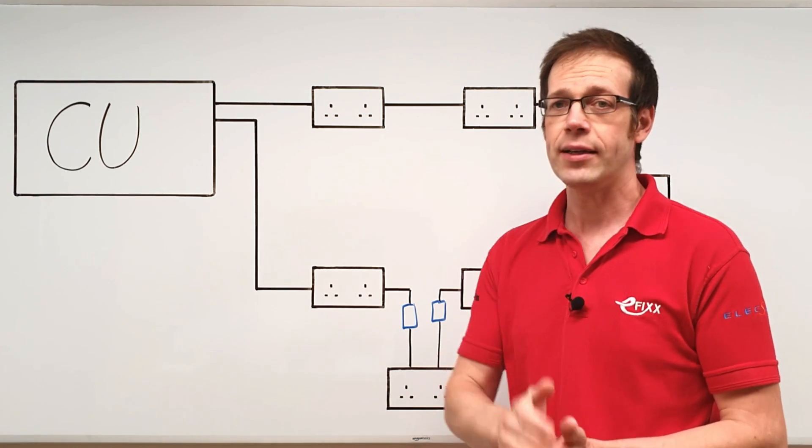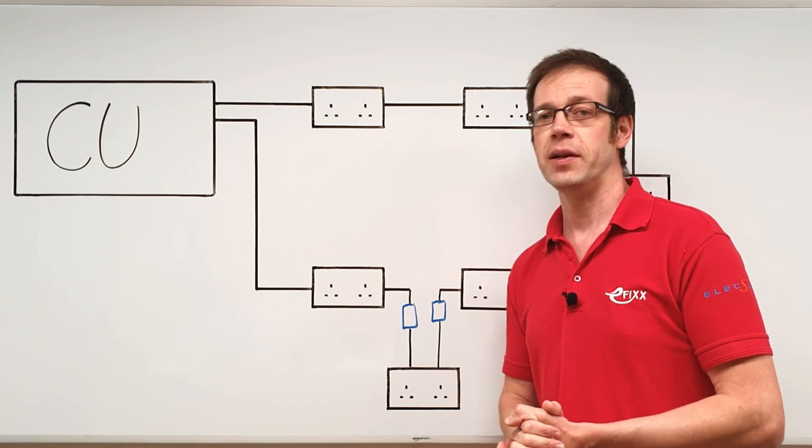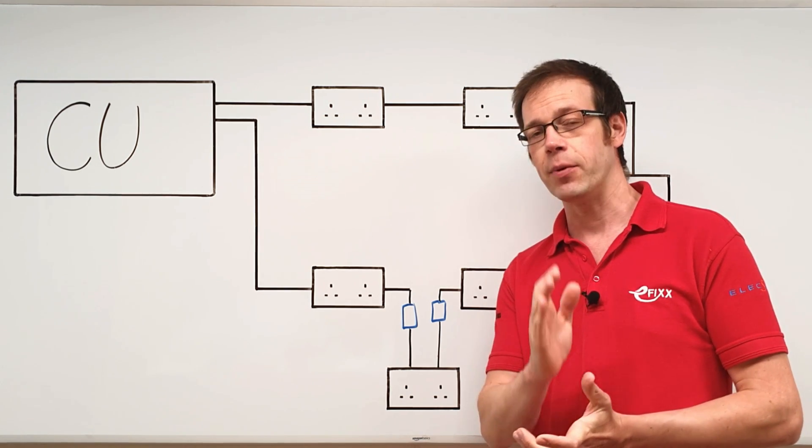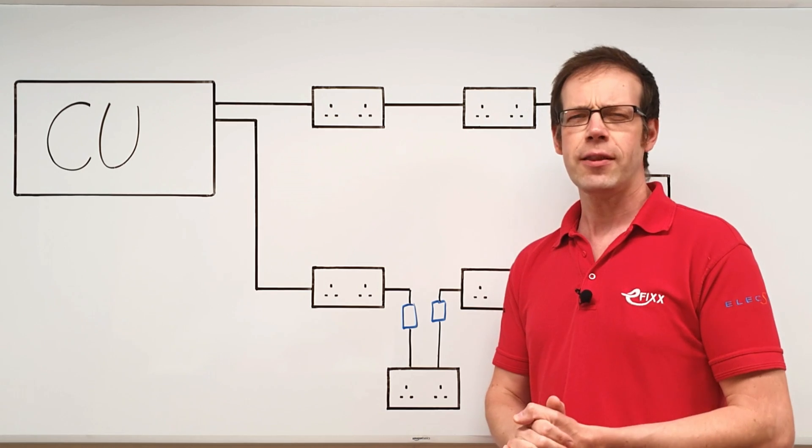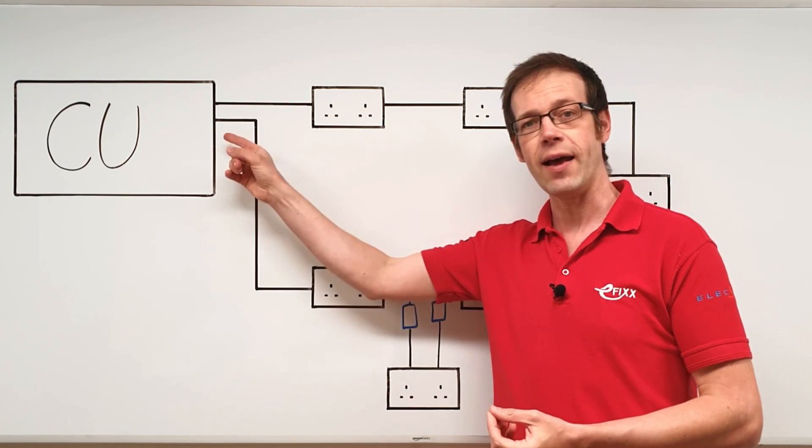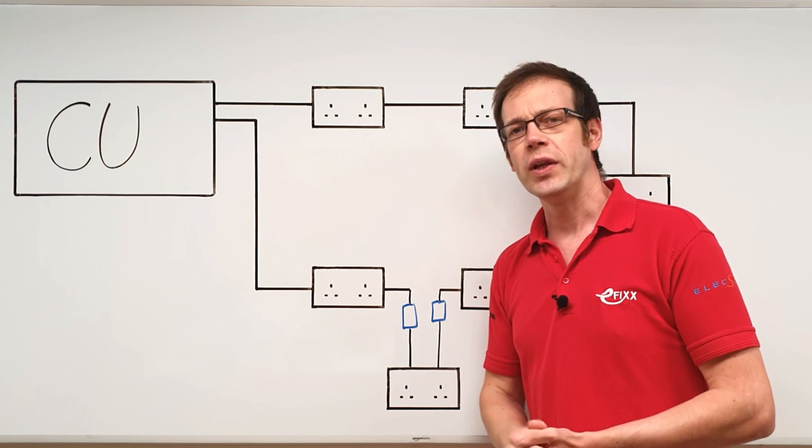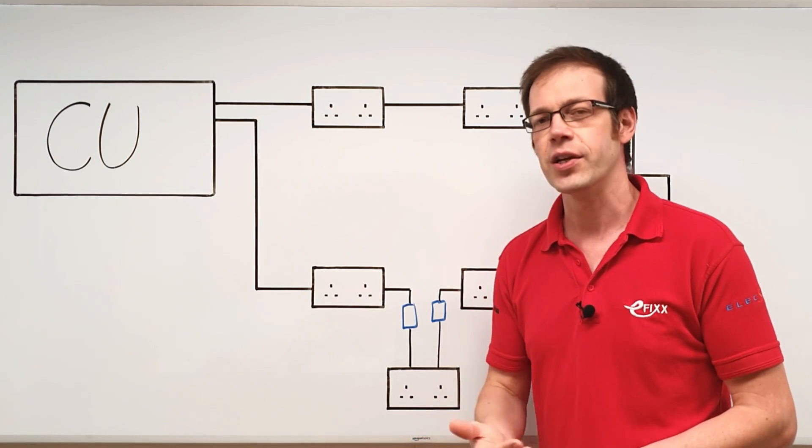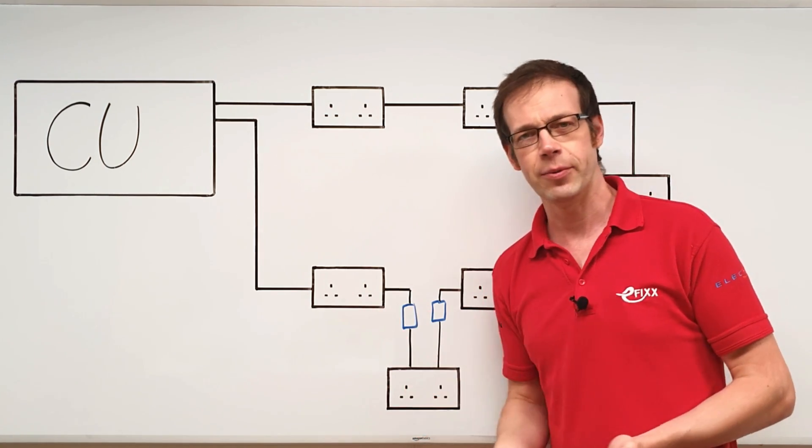Now, I'm sure you'll remember that a radial circuit wired in 2.5 millimeters squared can be protected by a 20 amp MCB. It's an interesting thought that when we convert to a ring, giving the electricity that additional path from the consumer unit, we don't double the amount of current the circuit can draw. You'll sometimes hear people say we've effectively doubled the cross-sectional area of the cable feeding this circuit by putting that extra leg in.